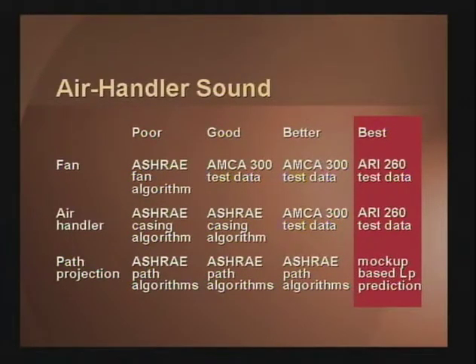The poorest level of information that's available that we can still find in the industry is simply using ASHRAE algorithm type methods for predicting the fan, the air handler, and making path projections. One step better than that for air handler sound would be to get fan tested data in accordance with AMCA 300 and then combine that with an ASHRAE algorithm to predict the sound of an air handler unit configuration. This is a common method being used by custom air handler manufacturers. The next step better is to use the AMCA 300 method, which is a standard for fans, but apply that to an actual air handler unit configuration. This method is fairly commonly used by manufacturers of catalog air handler units.